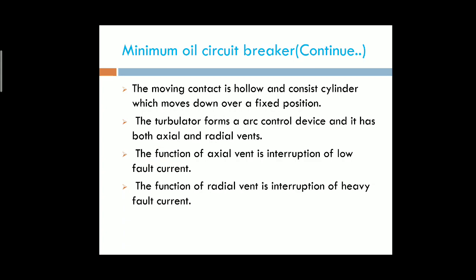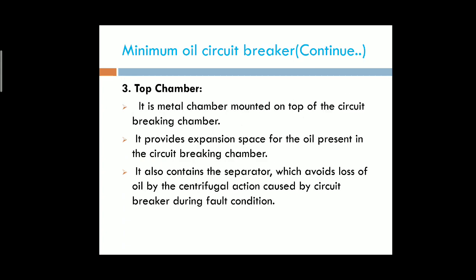It has both axial and radial vents. The function of the axial vent is to interrupt the low fault current, and the function of the radial vent is to interrupt the heavy fault current. Next, the last one is the top chamber.